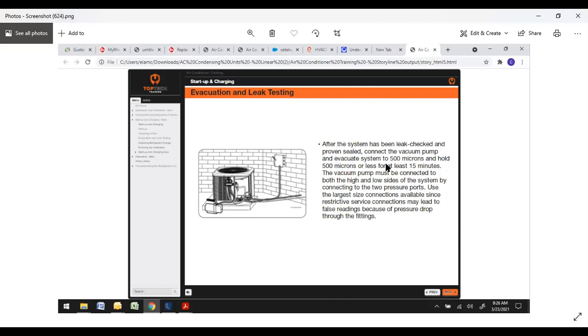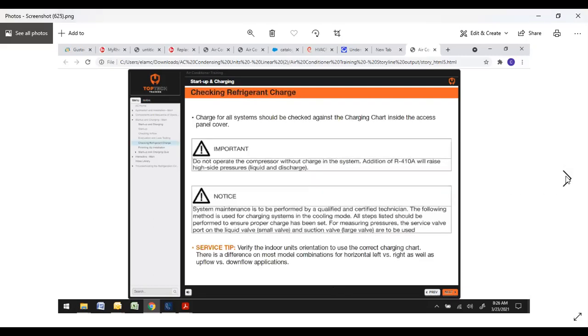So this goes back into the evacuation again. It is important once you get to your final 500, watch it, make sure it doesn't start rising back up again. If you get it to 500 and it starts climbing, climbing, climbing, you've got a leak, or a leak in your hose, a leak somewhere where you're letting moisture in, and that's what's killing your vacuum.